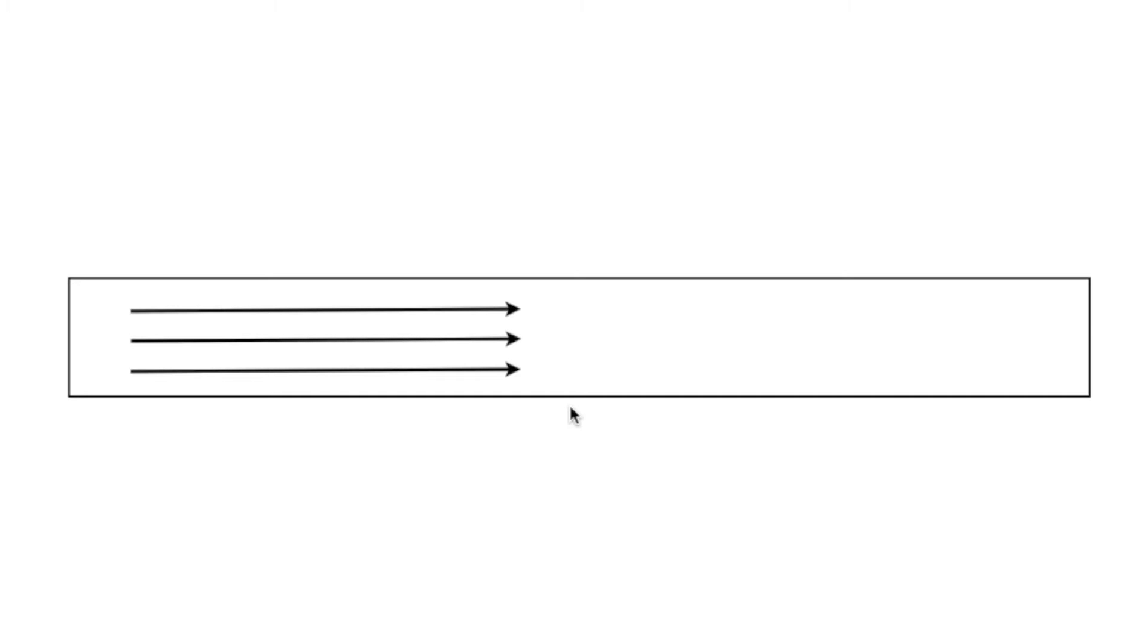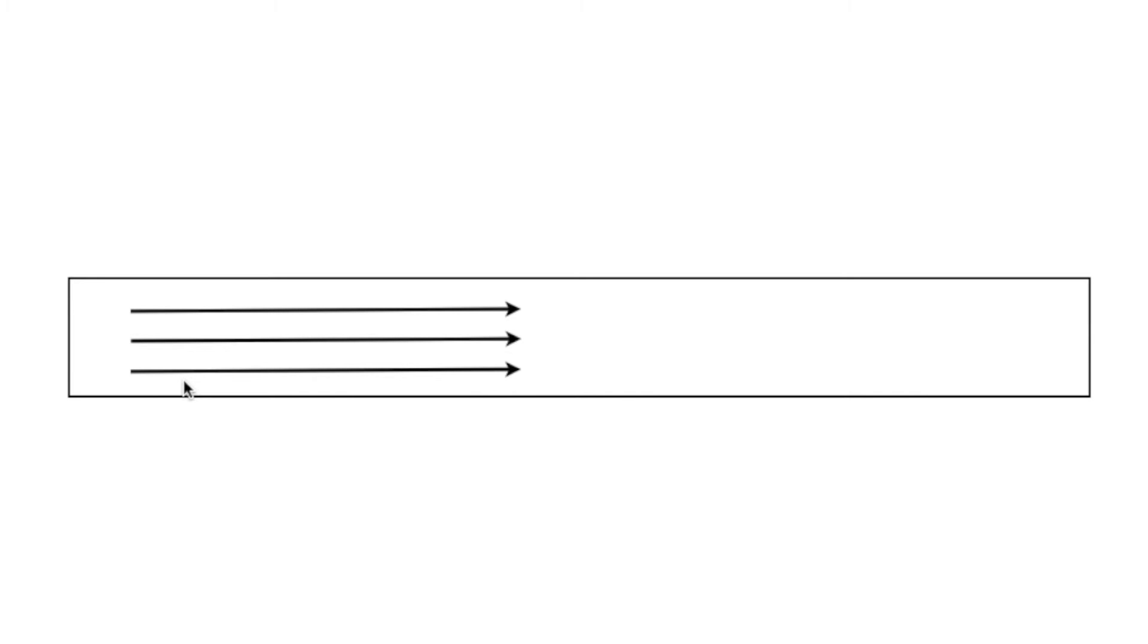So in the suction line we have to balance between the velocity of the gas and friction. So we create a suction line that's large enough to allow a small amount of friction with the line, which will increase efficiency, but we'll also have enough velocity to draw this oil with it.